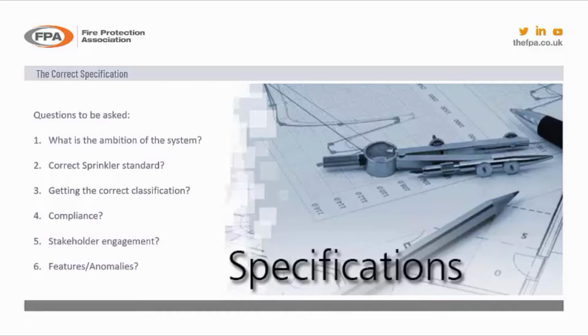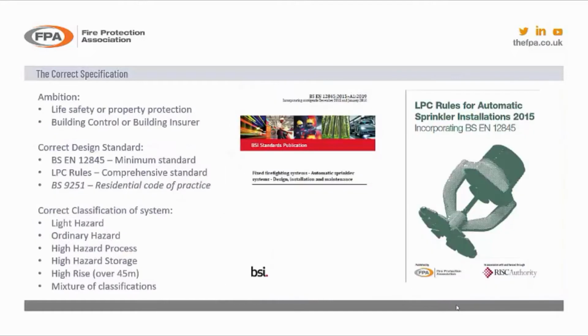As I've said, being involved in the industry for over 30 years, I've read specifications that have stated that it should be to BS EN 12845, it should incorporate the technical bulletins, it should incorporate NFPA, it should be to BS 9251, and finally, the insurers must be involved. This doesn't really specify what the system is, so at the beginning, the ambition of the system needs to be derived straight away to ensure that the specification is correct for the risk.